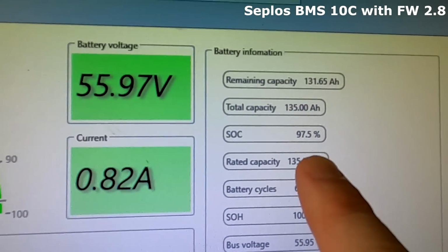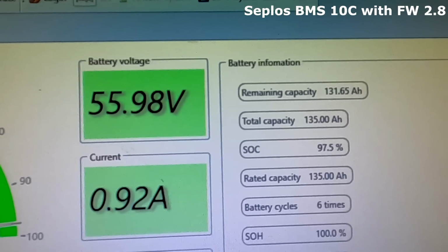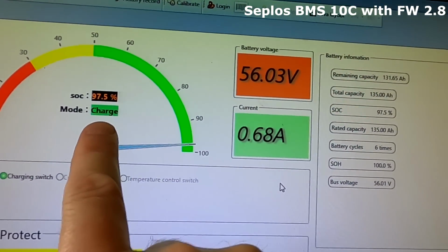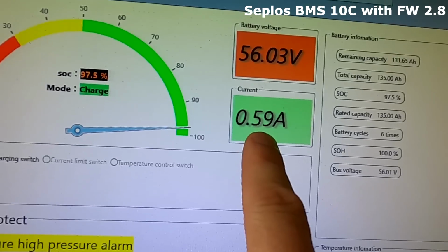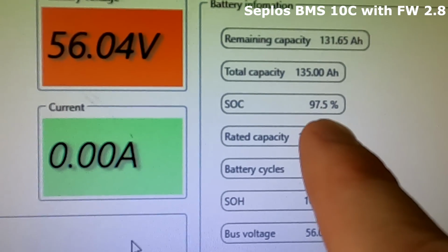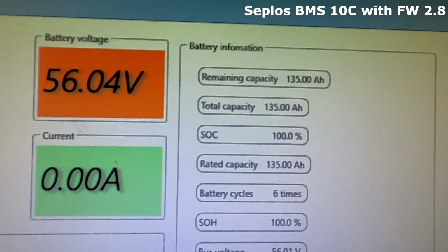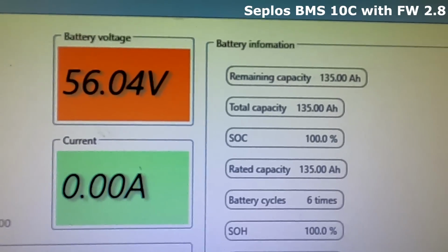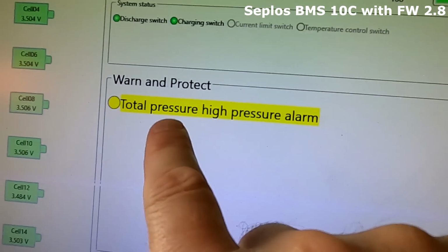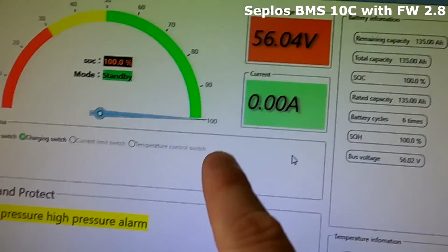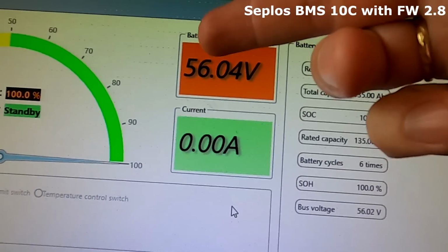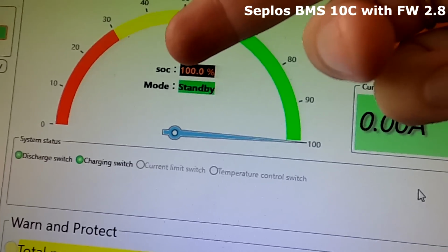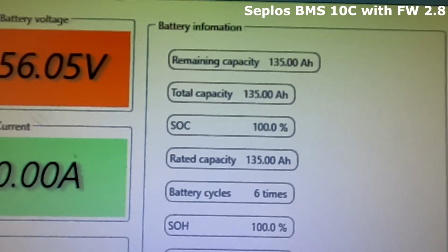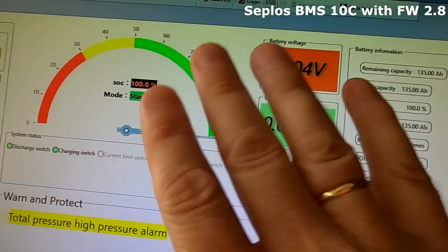As soon as we hit 56, watch the state of charge. Just wait until we go to standby, so when the current tapers off to zero, standby. There, 100%. Did you see that? It jumps to 100%. And it has nothing to do with the total pressure or high pressure alarm here - this is just what I was playing around with to see if there's a setting. But there's not. Obviously it's 56 volts, and then when the BMS goes into standby, it resets to 100%, regardless of what it was. But none of the settings I change has any influence on these 56 volts.